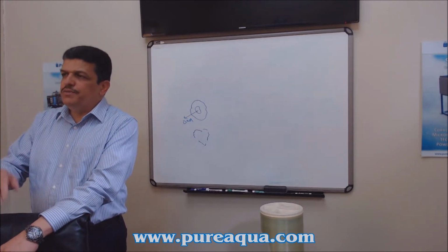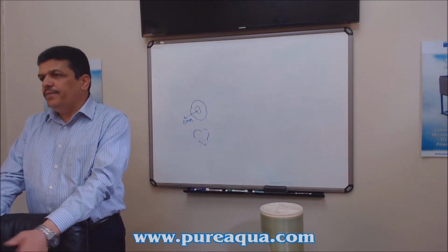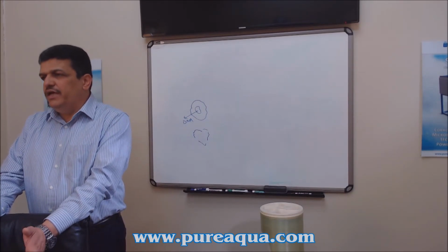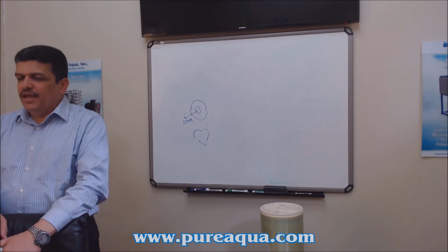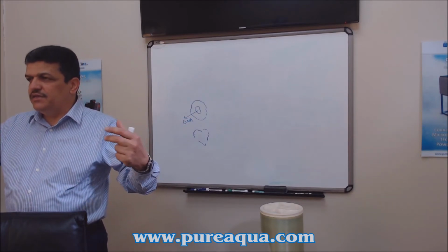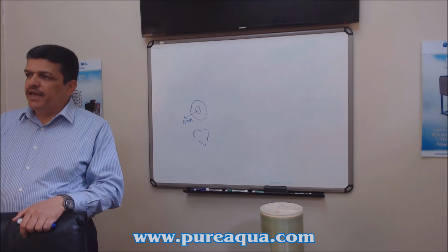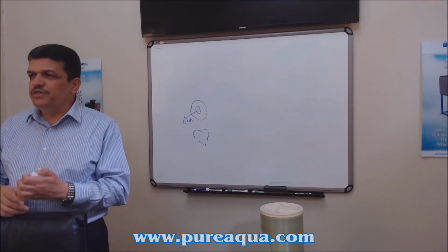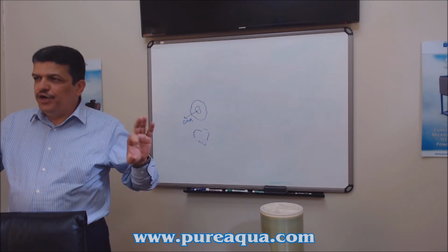When the intensity goes bad, it gives you a warning that it's time to change the UV. It's very easy to change the UV because you don't have to do any plumbing disconnect. There are some caps. You take them out and you just pull the lamp and disconnect the pin. Remember what we explained before, that the UV has the quartz sleeve first, then the light inside.